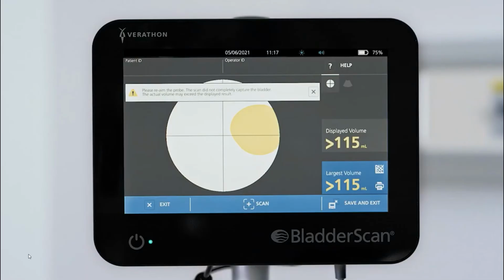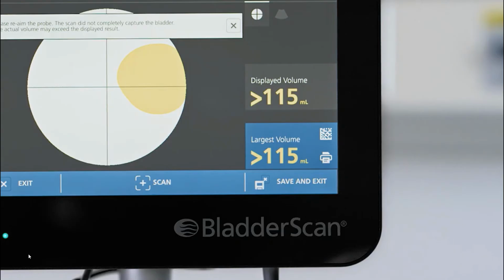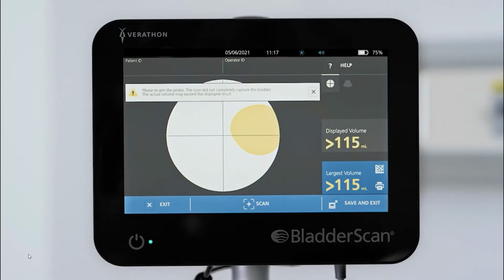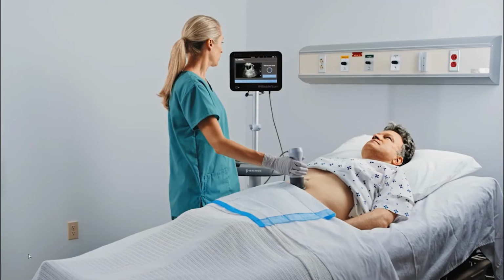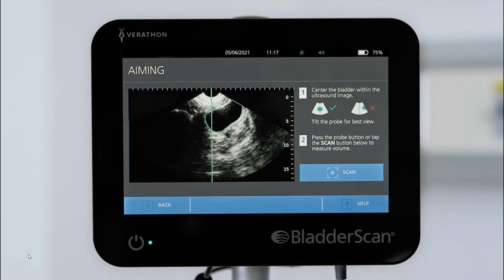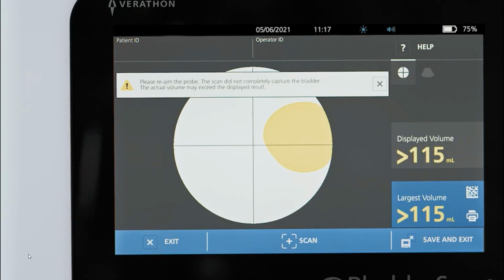If the bladder and volume number appear colored in yellow, the bladder volume has not been fully measured. The system also displays a greater than symbol before the volume number to indicate that the actual bladder volume may exceed the displayed result. Possible reasons include the following. Portions of the bladder extend beyond the edge of the scanned image.